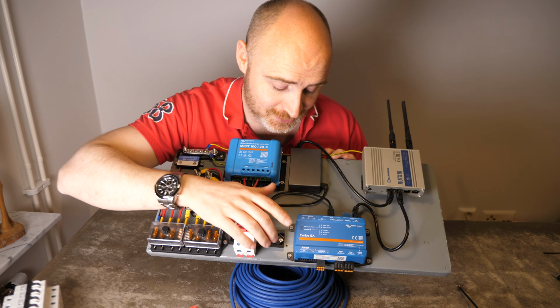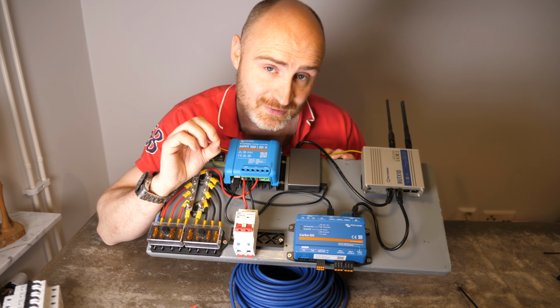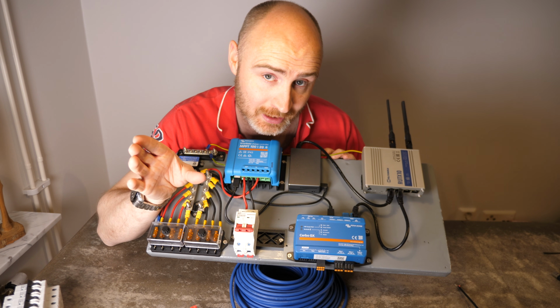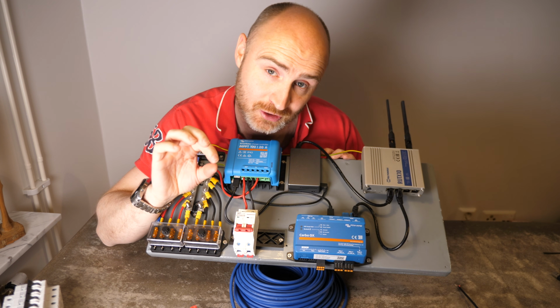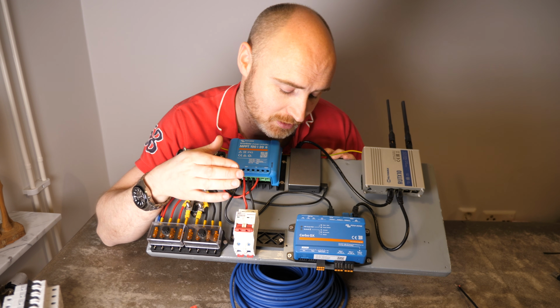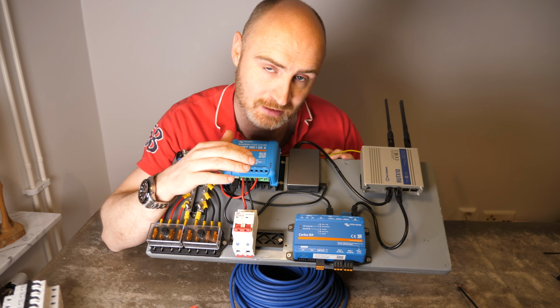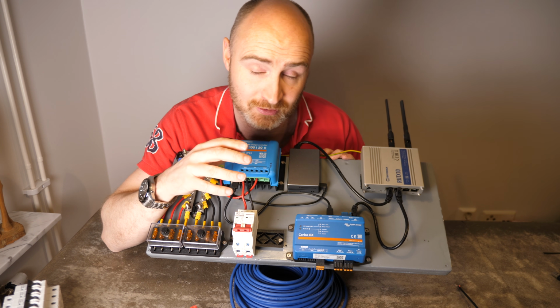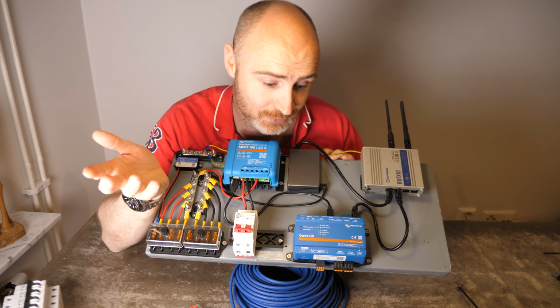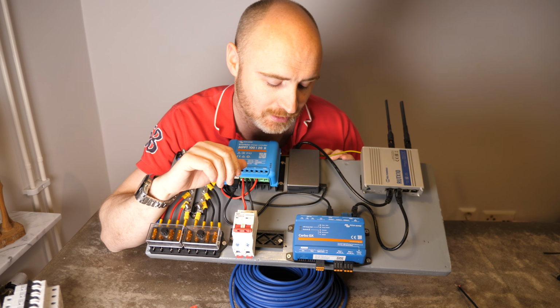So those were the temperature sensors I built, specifically because the wiring lengths were quite long, and you need that potentiometer on there to adjust the voltage return so that you can calibrate all the temperature sensors so the temperature reading will be accurate and not out by any number of degrees.